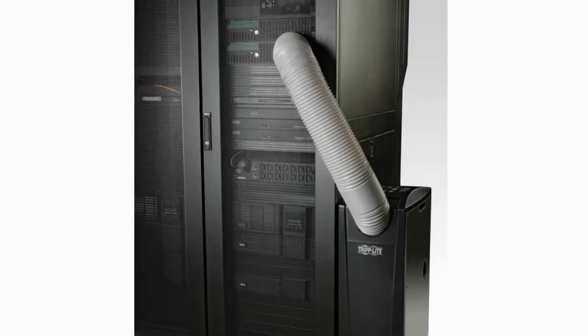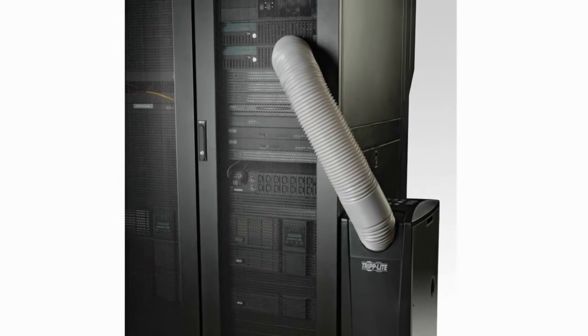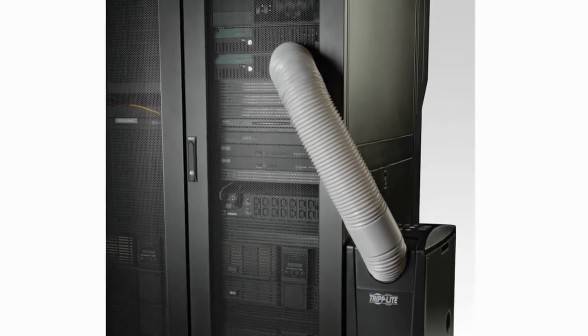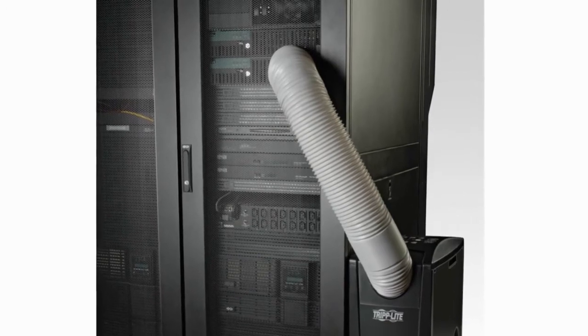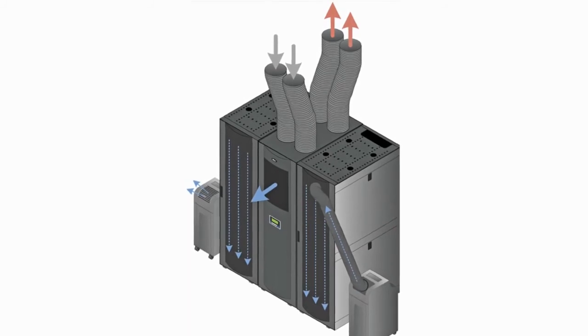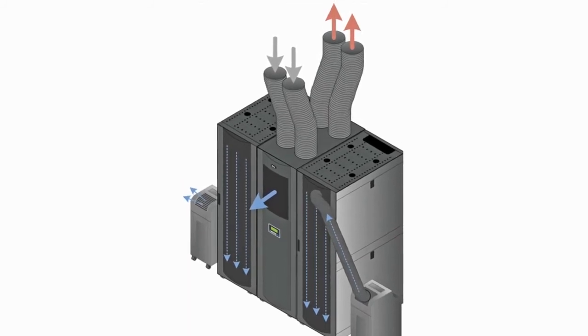Now you can position the cooling tube wherever it is needed. If you plan to cool a rack enclosure, place the end of the cooling duct over a perforated area near the top of the enclosure's front door, or near the top of the bank of equipment that requires cooling. Cool air will sink and spread across the air intakes at the front of the rack enclosure.